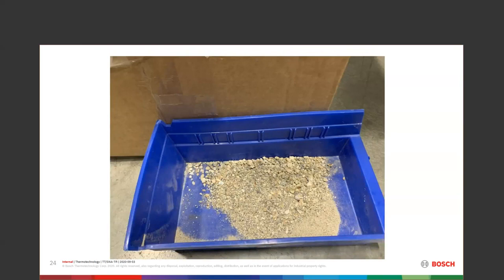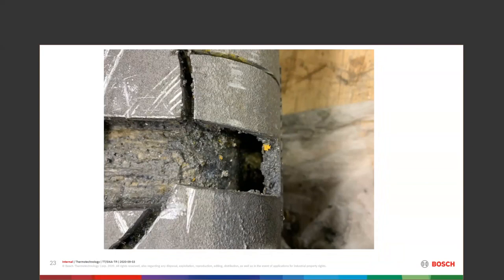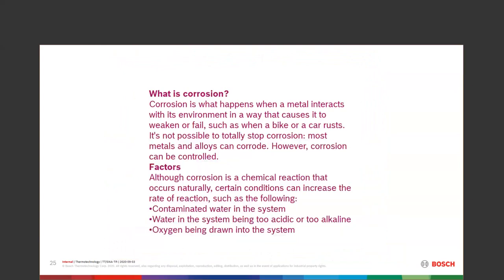We gave that customer a new heat exchanger, a new block — but we won't give a second one unless we fix the water. The big reasons for fixing water are efficiency, efficiency, and longevity. Corrosion itself occurs when we have aggressive water: low pH, high pH, oxygenated water, or chemicals like sodium chlorides in the system.